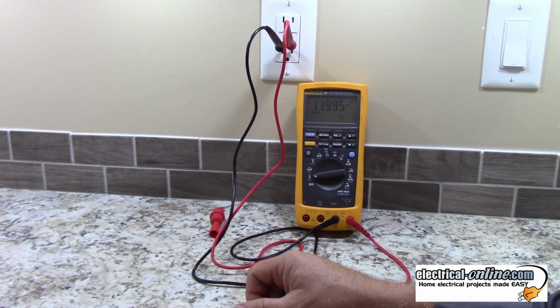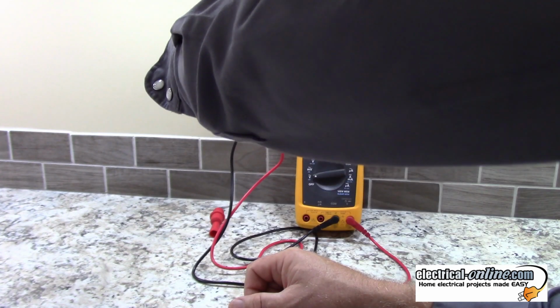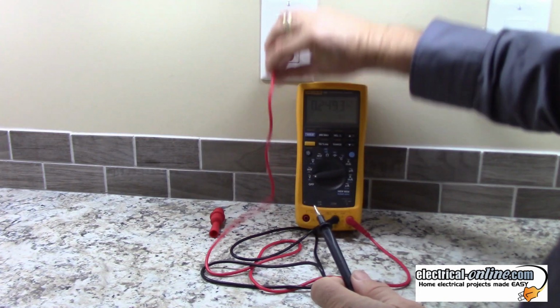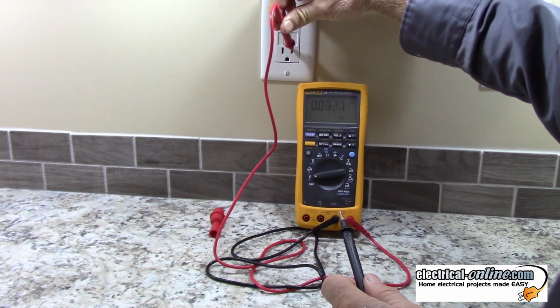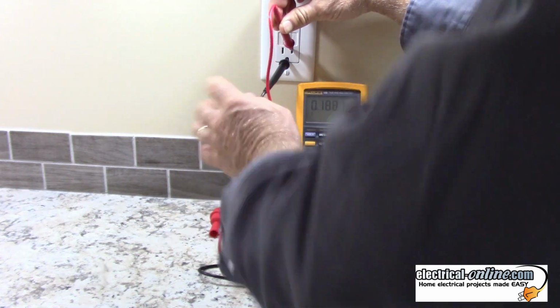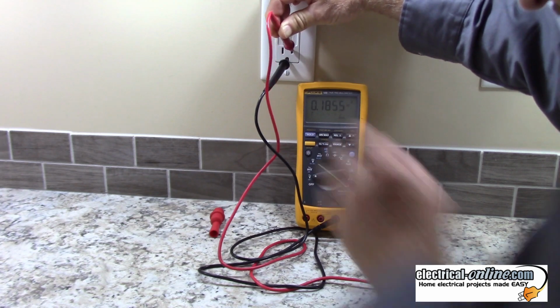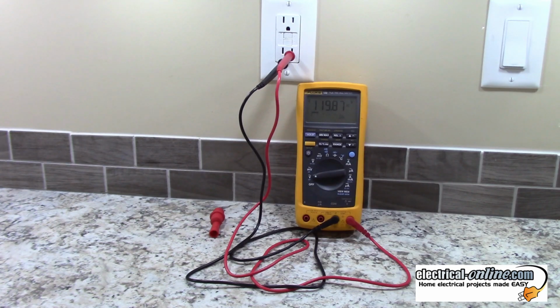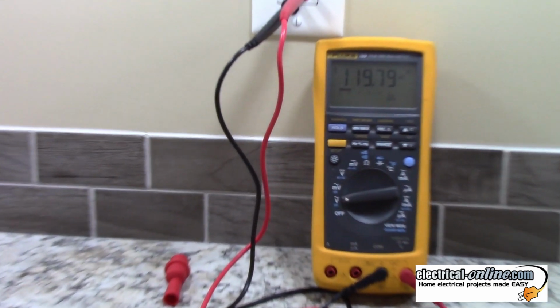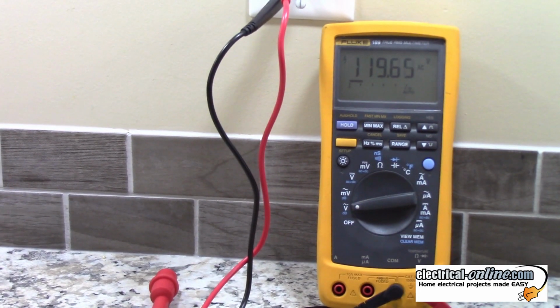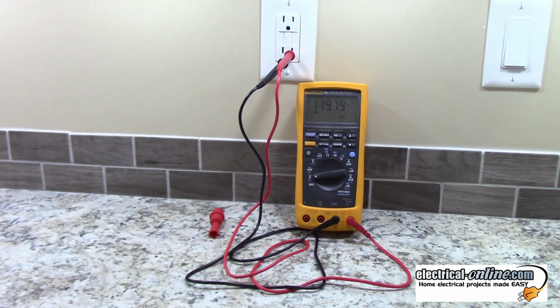So now we'll check hot to ground. So we'll leave the probe in the hot terminal, and we will touch the black into the ground. Make sure we got a good connection in there. And now you can see with the red lead in the hot prong of the receptacle and the black on the ground, we've got 119.6 or 7 volts, the same as we had hot to neutral, what you'd expect.